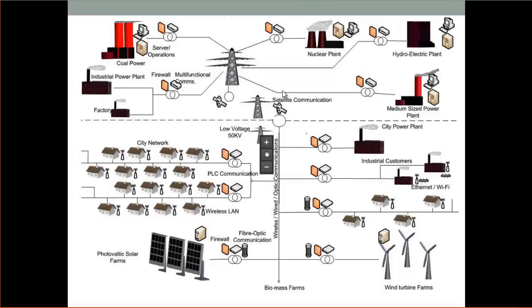So, that afternoon peak comes, and at 3 o'clock you're going to need the extra power. So you start up that gas turbine, and you start making some power. So all the traditional fossil-based generation or nuclear-based generation has the advantage that you can send a signal to that plant and tell it how much to make, and it'll make that much. And so over time, I drew those load profile curves, and power companies keep track of how much power they produce at any given time, and they run these predictive models. Maybe it's a neural network model or something, but they run these predictive models, and so they have a pretty good idea based on what time of year it is and the historical load and what the weather report says. They can make a pretty accurate estimation of what the load profile is going to look like tomorrow.